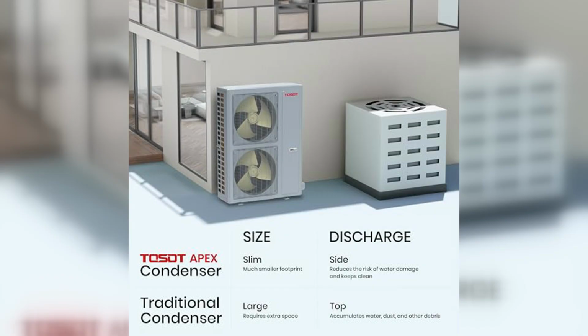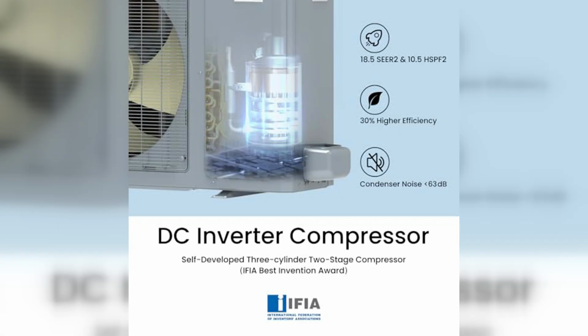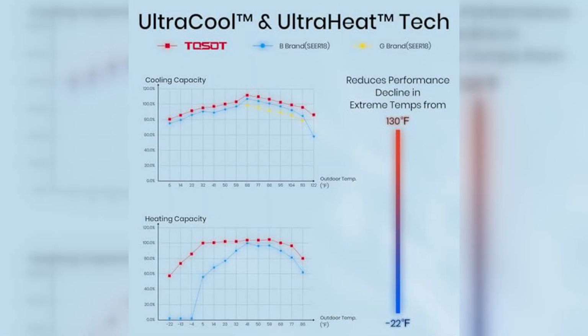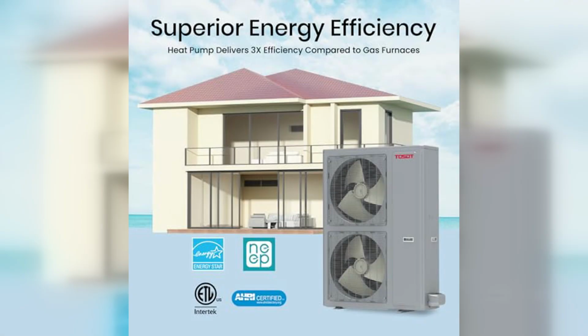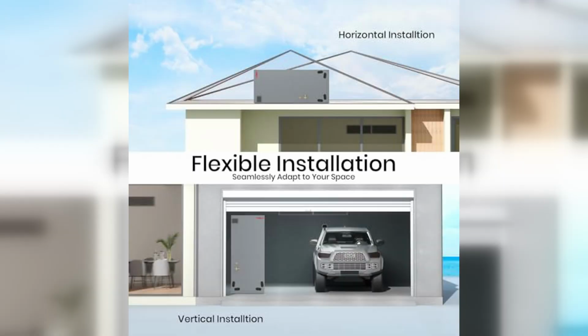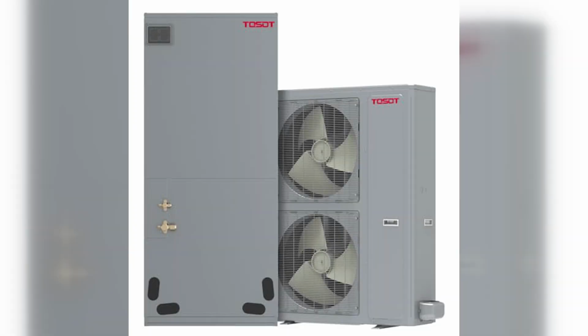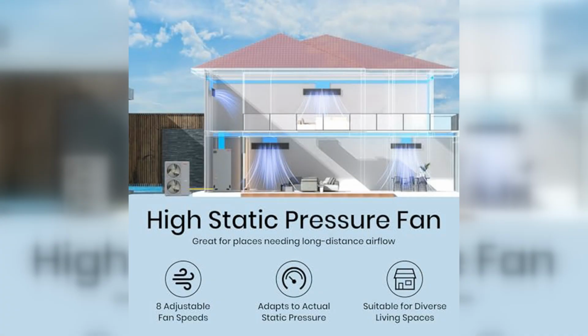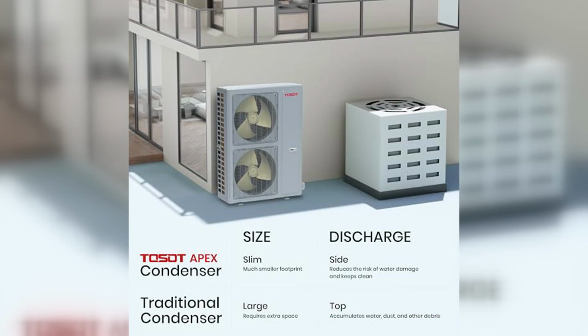Beyond comfort, the 18.5 SEER2 rating places this in a good bracket for energy efficiency, which is a critical consideration given that a 5-ton unit is going to be one of the largest consumers of electricity in your home. The ultra-heat and ultra-cool marketing points are a reflection of its performance envelope, which is rated to handle outdoor temperatures anywhere from -22 degrees Fahrenheit up to 130 degrees. That wide range is a testament to the vapor injection technology in the compressor, which keeps the system viable in much colder climates than traditional heat pumps would ever dream of touching. If you live in an area that sees brutal winters but you want to move away from a gas or oil furnace, this is the kind of system that makes that transition possible.